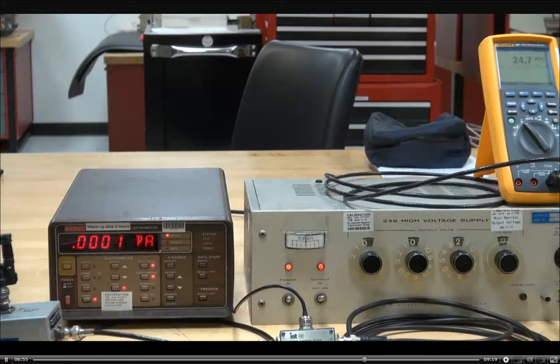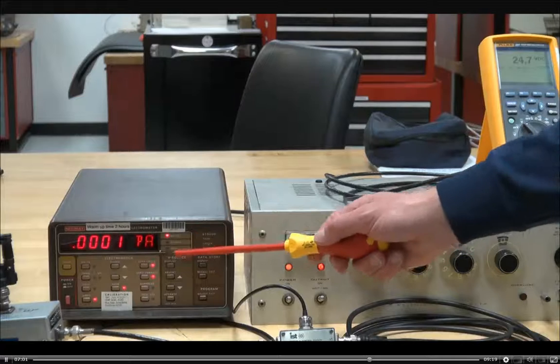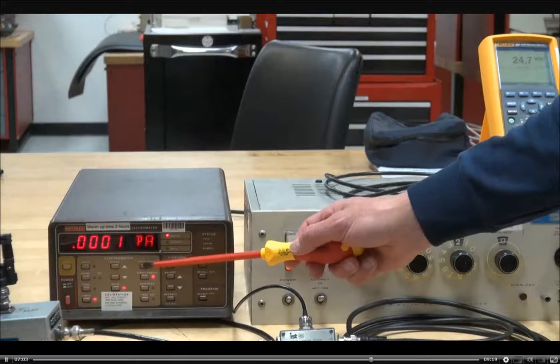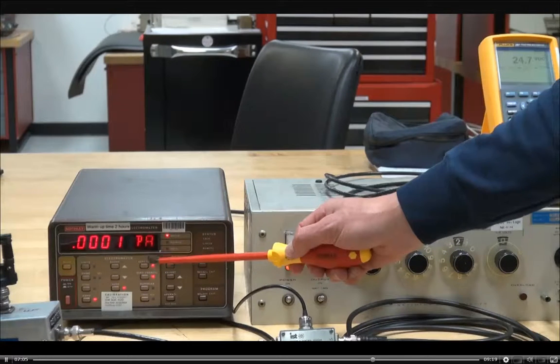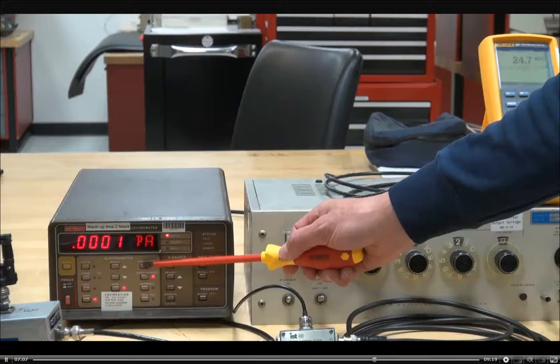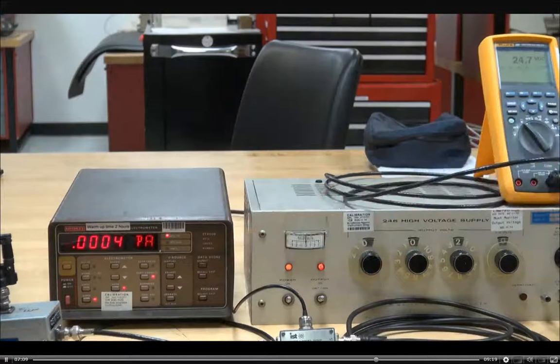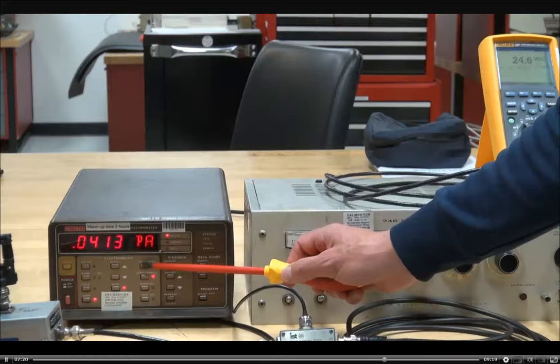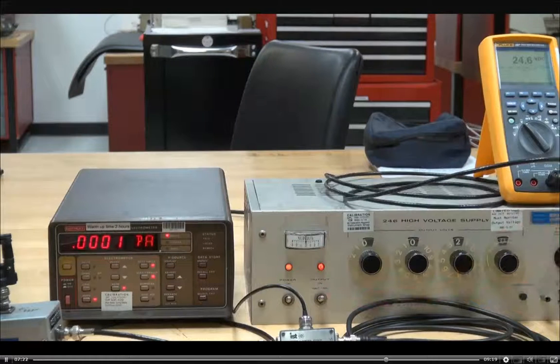We'll wait 1 minute. And using our insulating tools, we're going to turn off the zero check on the electrometer. So we're going to assume the 1 minute has elapsed. And we have a reading of 0.0004 picoamps. Turn your zero check back on and go to your next setting.